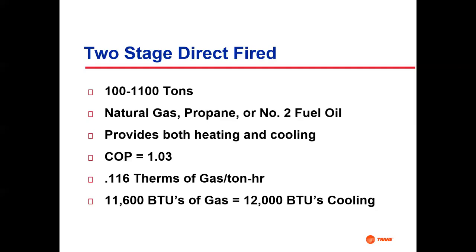These systems can provide heating and cooling. You can do heat recovery from this that can provide hot water for space heating. Now it's interesting, if you're going to size the system, are you going to size it on heating and just take what cooling you get? Are you going to size it on cooling and just take what heating you get? You can pick one, but you can't pick both, because the cycle depends on it. If you pick a cooling capacity, then you get a certain amount of waste heat that you can recover and use.